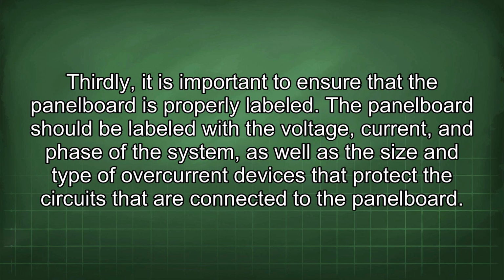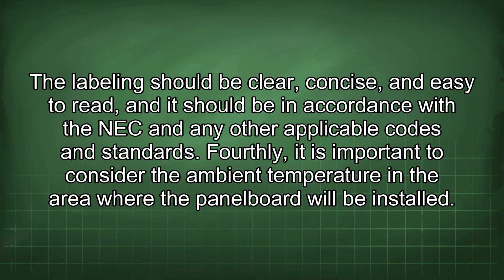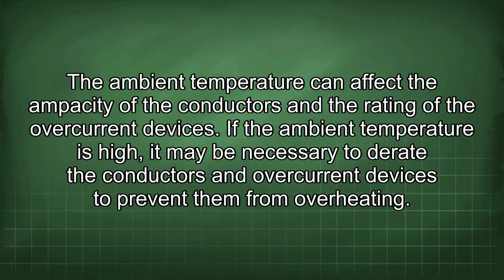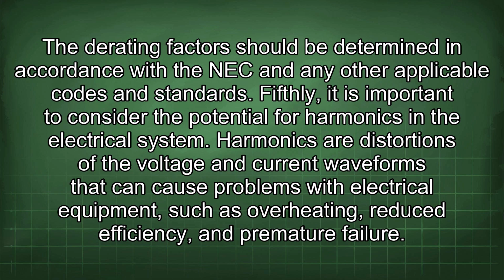Thirdly, it is important to ensure that the panel board is properly labeled. The panel board should be labeled with the voltage, current, and phase of the system, as well as the size and type of overcurrent devices that protect the circuits that are connected to the panel board. The labeling should be clear, concise, and easy to read, and it should be in accordance with the NEC and any other applicable codes and standards. Fourthly, it is important to consider the ambient temperature in the area where the panel board will be installed. The ambient temperature can affect the ampacity of the conductors and the rating of the overcurrent devices. If the ambient temperature is high, it may be necessary to derate the conductors and overcurrent devices to prevent them from overheating. The derating factors should be determined in accordance with the NEC and any other applicable codes and standards.